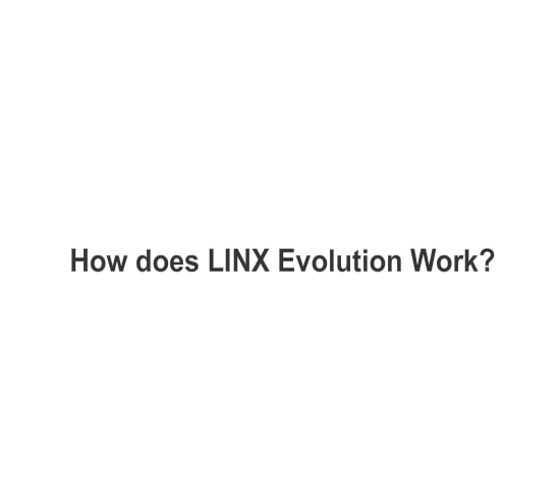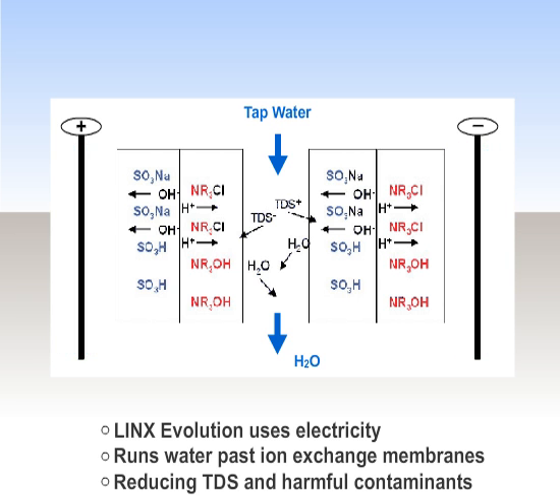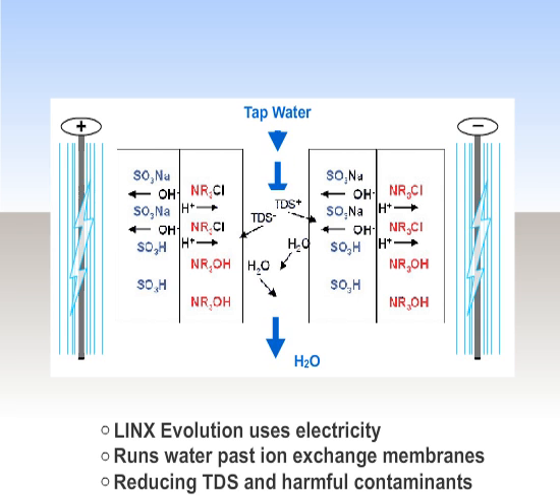How does the LINX Evolution work? Rather than using pressure to force water through a membrane, the LINX Evolution uses electricity to run water past special ion exchange membranes — not through them — efficiently reducing TDS and harmful contaminants while creating minimal water waste.